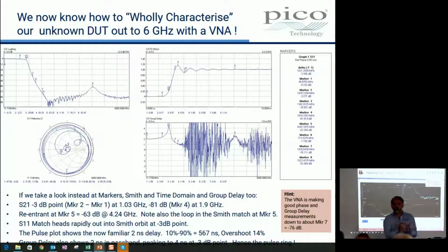So, can it ring a bell? Yeah, it works. It can ring a sound, and did you see it put a little squiggly marker around where the first limit failure was occurring? So it highlighted it, and it can make a sound. Or you can read it back over the remote. So over remote control, you can pick up the limits failure as well.